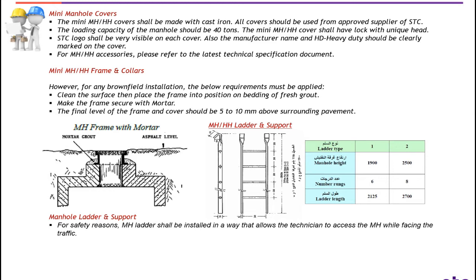Mini manhole handhole frame and collars. Before delivering mini manhole to the site, the manufacturer should ensure that the collar has to be prepared to accept the frame and cover after the initial curing period is complete. Frame as well as cover of the mini manhole has to be cast iron steel. Furthermore, the delivered pre-fabricated handhole already has a pre-installed galvanized steel frame. The thickness of this frame is 5 mm. The frame shape has to have less welding parts, well fixed to the handhole.